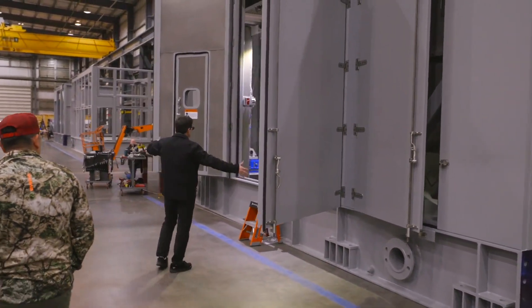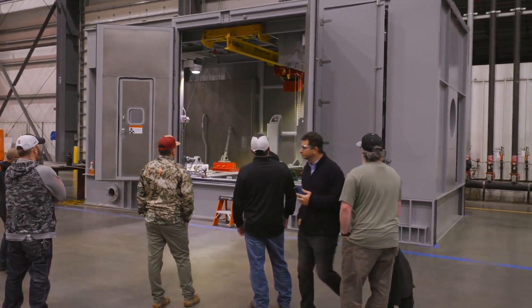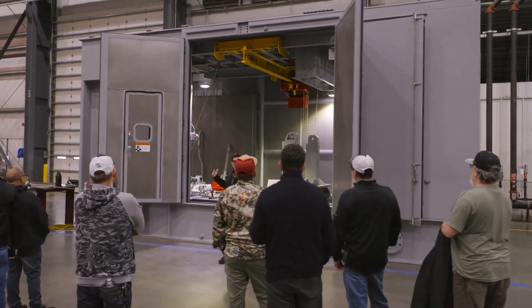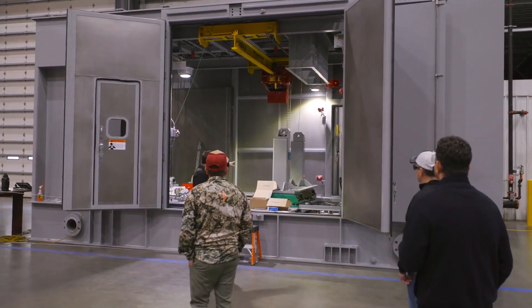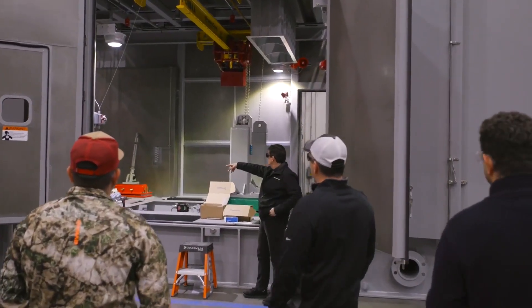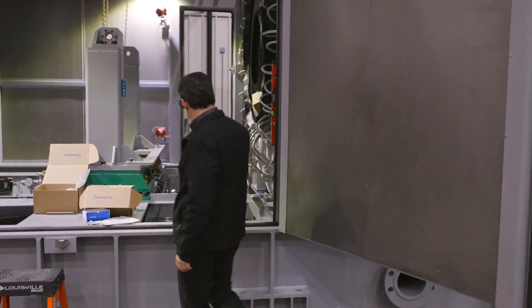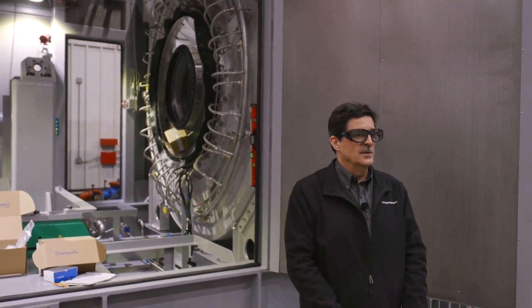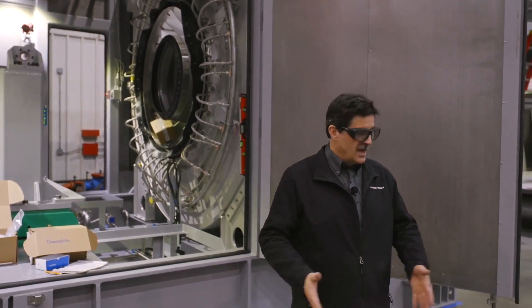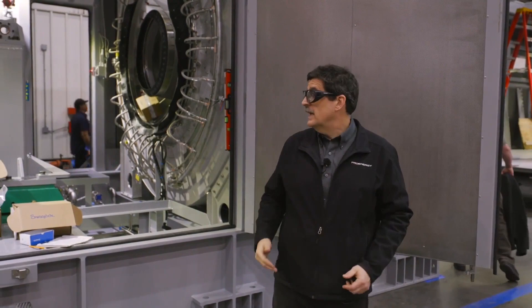We made our main doors just a little bit bigger because we could. They cost a little bit more, but because we make them ourselves the cost is relatively small, and it gives better access to get the engine in and out. You can see the main inlet volute which turns the air from the inlet down along the length of the gas turbine, and the front and rear legs — the rear leg turnbuckles are all manufactured in our ARM facility. We also lay out the floor so there's room for someone to go down into the floor and service the equipment. We put everything to the edges so there's room to access and service the equipment — another key element of what we do.